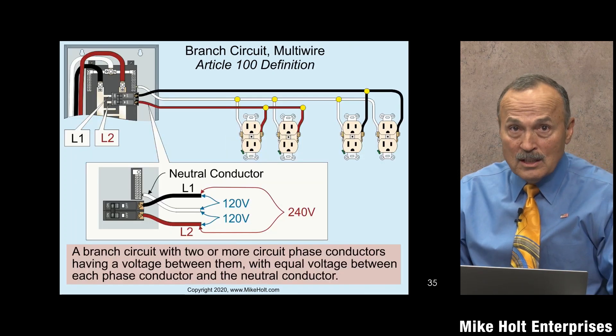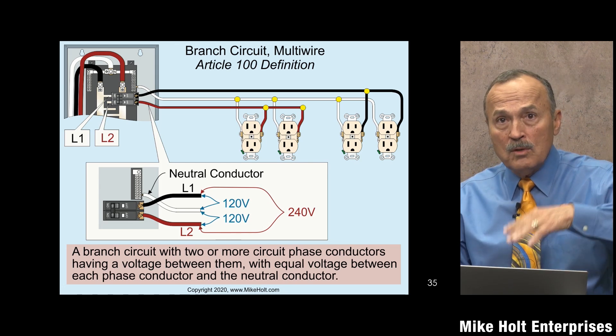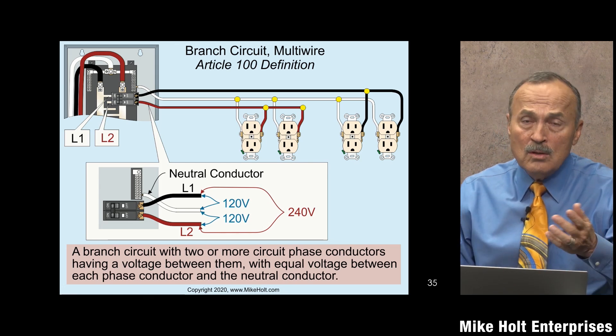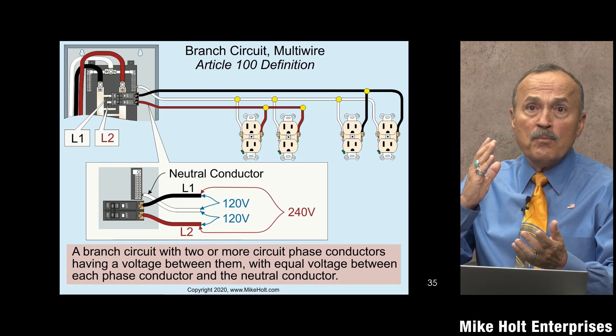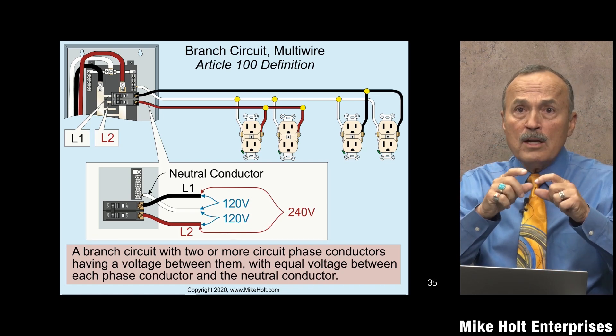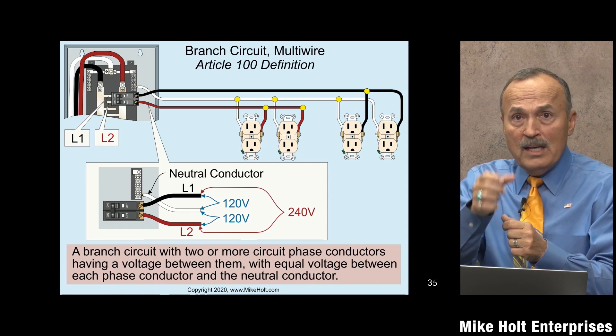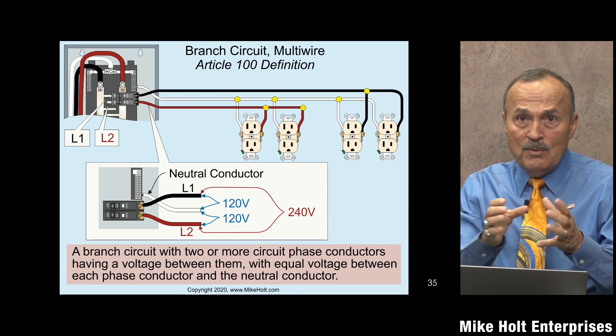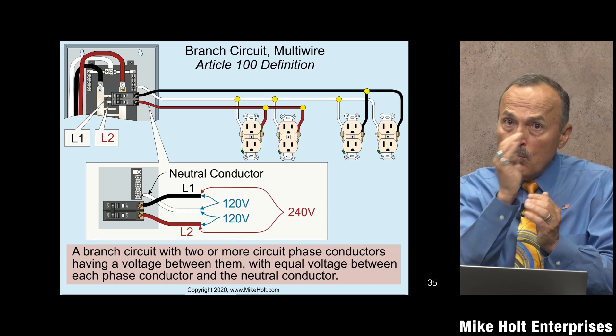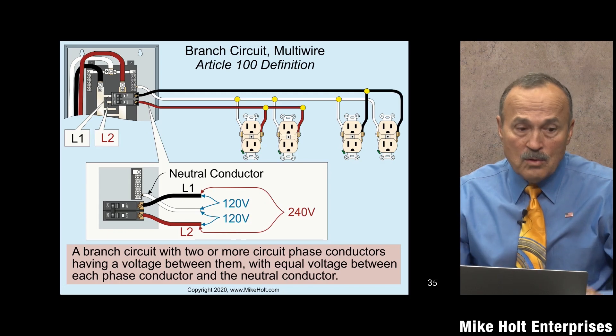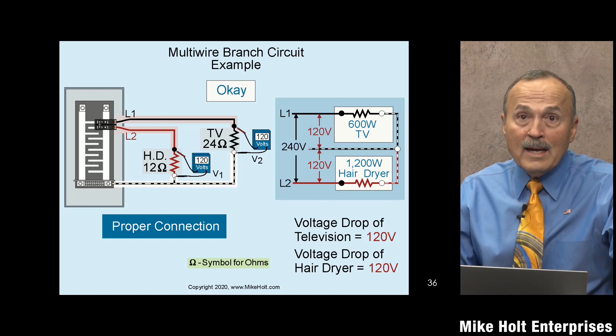So we know what a multi-wire branch circuit is: originating from the same panel, two hots and a neutral, or three hots and a neutral. The key rules are: all conductors must come off a common breaker or breakers with handle ties, and you must group the phase conductors and neutral conductors together — unless it's obvious — so you can trace those wires to a breaker. As Jennifer noted, grouping enables lockout/tagout so you can disconnect all phase conductors simultaneously.